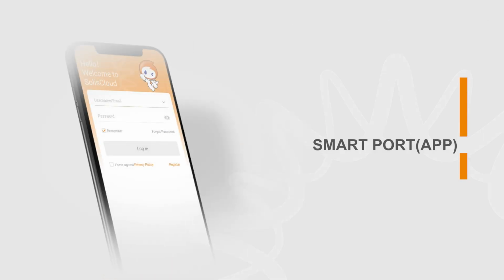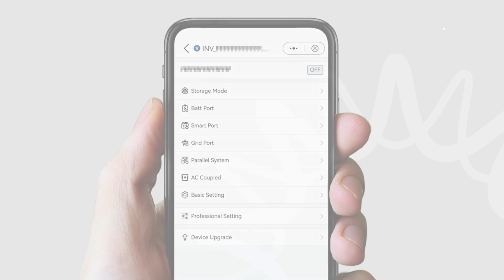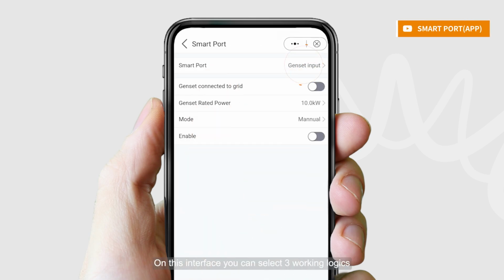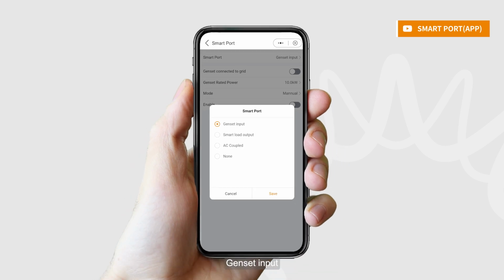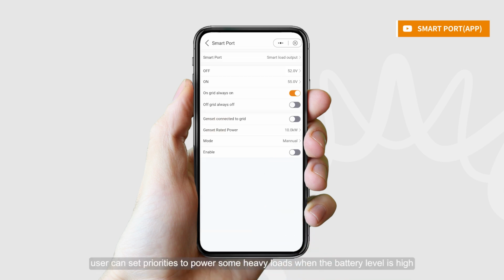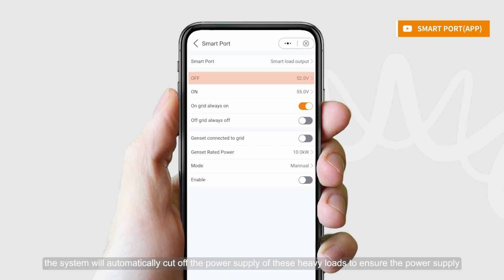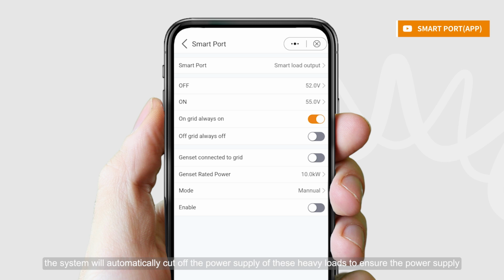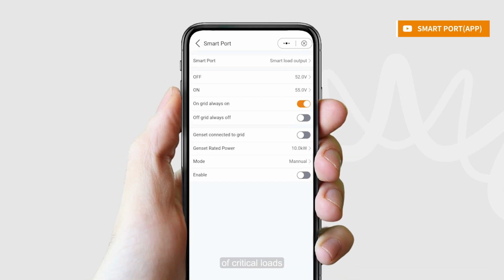Smart Port. Click on Smart Port. On this interface, users can select 3 working logic: genset input, smart load output, and AC coupled according to the actual connection. With Smart Load function, user can set priorities to power some heavy loads when the battery level is high. When the battery level drops to off value, the system will automatically cut off the power supply of these heavy loads to ensure the power supply of critical loads.